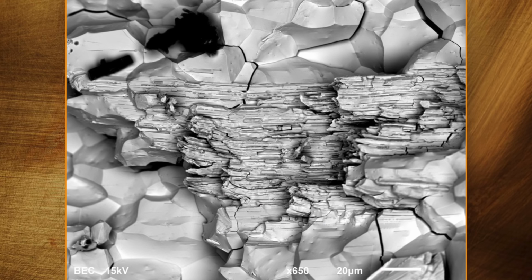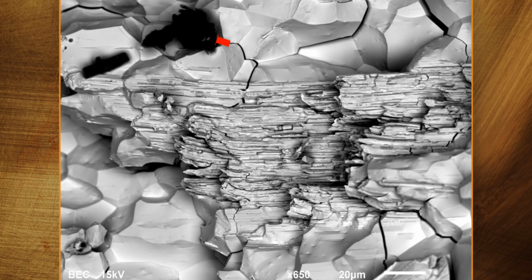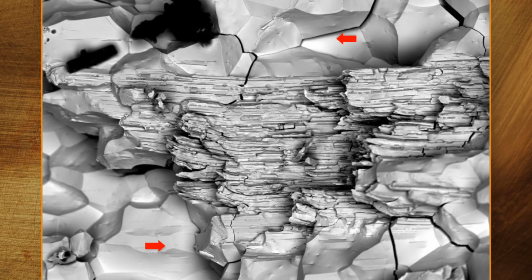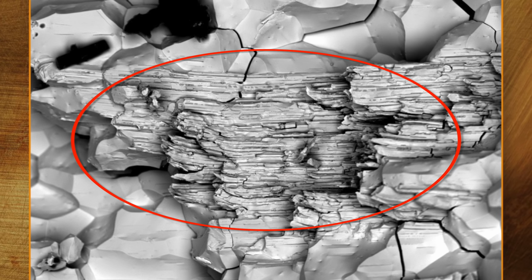And I'm going over the material in the tungsten. If you know anything about materials, what you're looking at here, well, the black stuff could be contamination. But the kind of geometrical shapes that you see there above that other stuff that looks like shale is tungsten. It looks like it was getting melted. That shale isn't how it normally looks, but this is on the inside of the tip. On the outside of the tip, it wasn't being affected at all. Not at all. When we did the SEM, it was coming back that it was tungsten. The crystalline structure looked just like it should. We looked inside, and this is what we found, and we found a lot more.